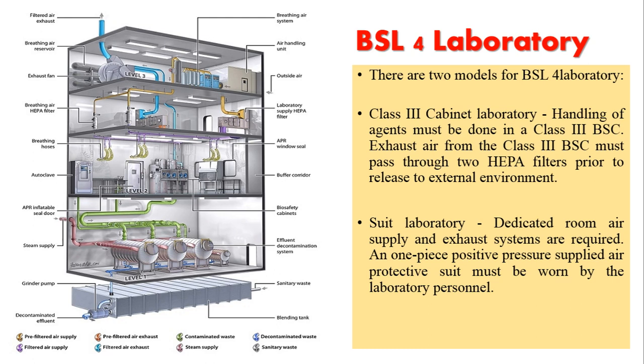BSL-4 laboratories are very complex and expensive to construct. There are two types: Type 1 is a Class 3 cabinet laboratory, where all agent handling is done inside Class 3 biosafety cabinets and exhaust air must pass through two HEPA filters before release to the environment. Type 2 is a suit laboratory, where personnel working inside use a positive pressure suit.